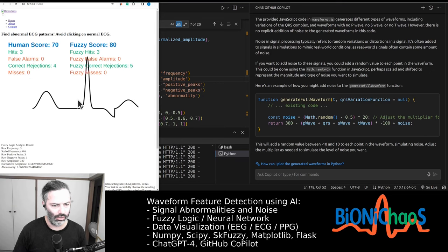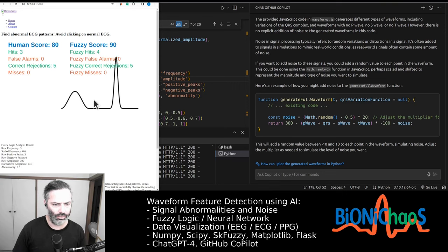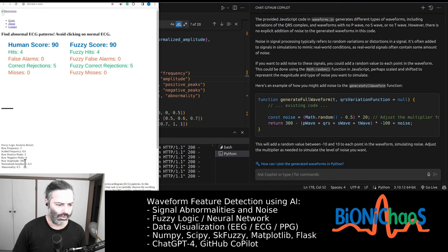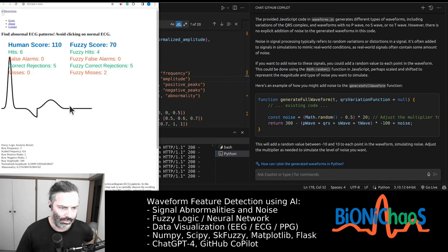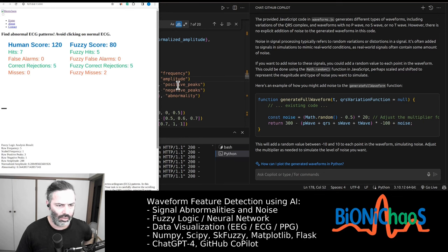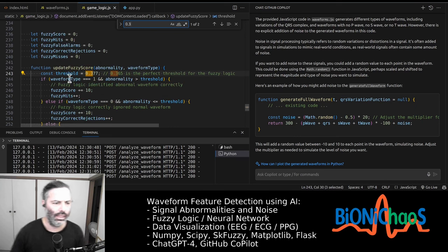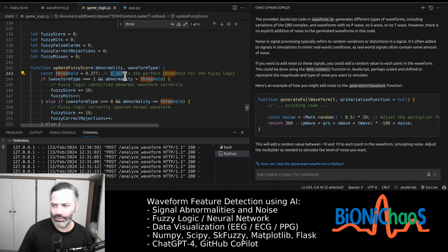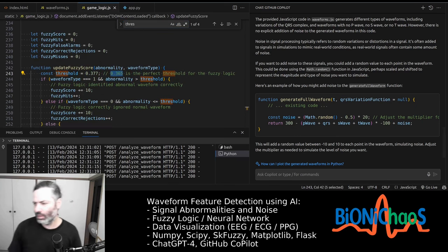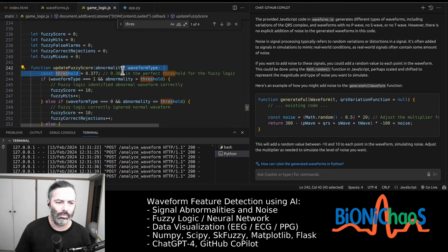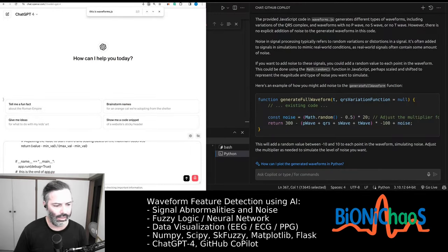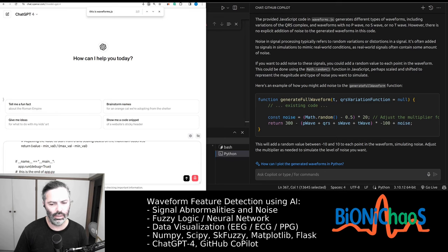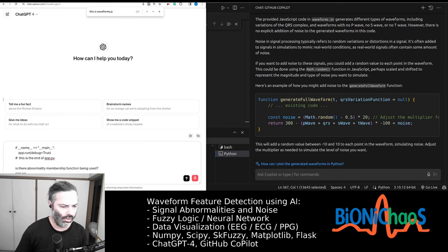It is just seeing the raw data, just seeing the waveform, nothing else. It's making this decision. It's currently set on purpose to always make a mistake, to miss, because of that threshold. Yeah, it made a miss. We can quickly fix that by adjusting this threshold back to 0.365. Then it will never make mistakes again.